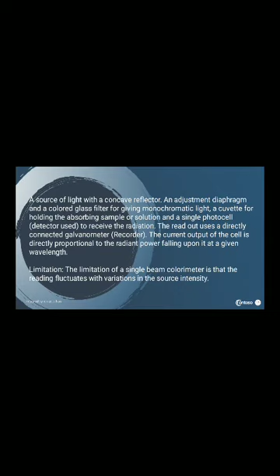A source of light with a concave reflector, an adjustment diaphragm, and a colored glass filter for giving monochromatic light, a cuvette for holding the absorbing sample or solution, and a single photocell detector to receive the radiation. The readout uses a directly connected galvanometer, that means a recorder. The current output of the cell is directly proportional to the radiant power falling upon it at a given wavelength. The limitation of the single beam colorimeter is that the reading fluctuates with variation in the source intensity.